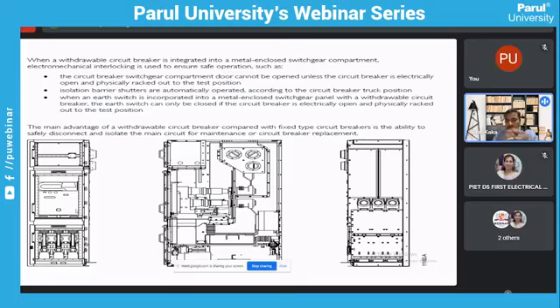This is just an overall architecture of a medium voltage switchgear. Can you all see my cursor here? Yeah. So whenever a withdrawable breaker is integrated in a metal enclosed switchgear, it fundamentally has a breaker compartment, busbar compartment, cable compartment, VT compartment, and LV door compartment.